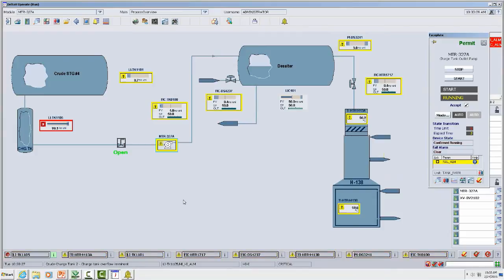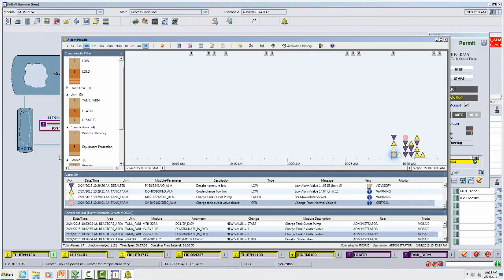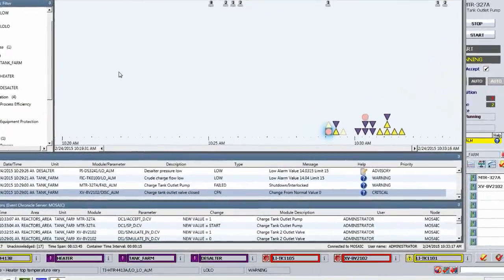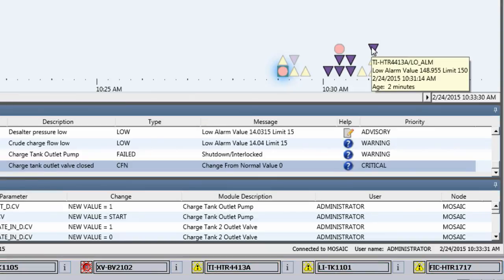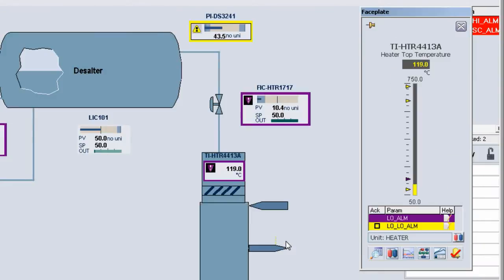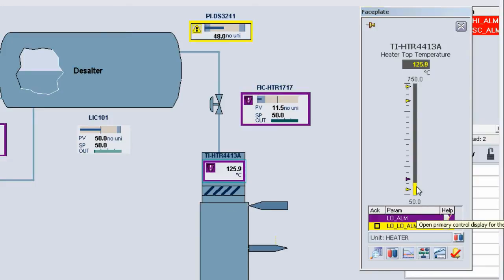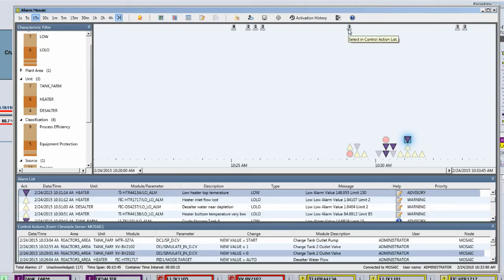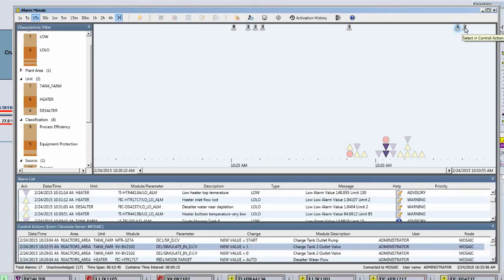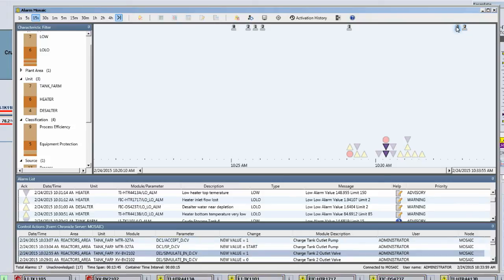And let's watch the alarms clear in Alarm Mosaic. I'll stretch out the pattern of alarms to give you more of a sequential view. Many of the alarms are closing out, but not all. The operator might want to understand what's happening with the remaining active alarms. Let's open a faceplate and we can see that the process is coming around to a normal condition, so that alarm should clear relatively soon. Notice also that in addition to capturing the control actions that precipitated the flood, the operator's corrective actions are also appearing in Alarm Mosaic, so you can tie together the whole thread of actions and alarms.